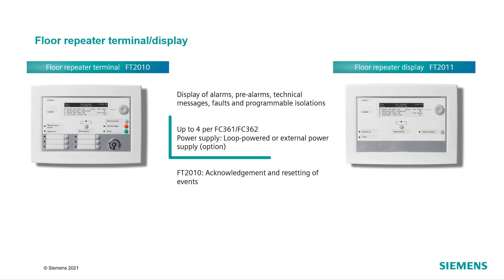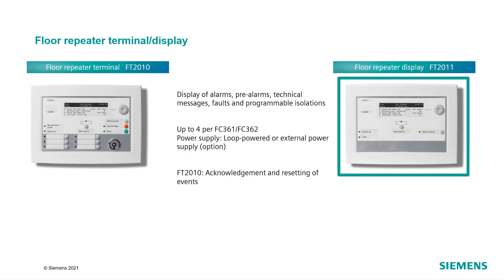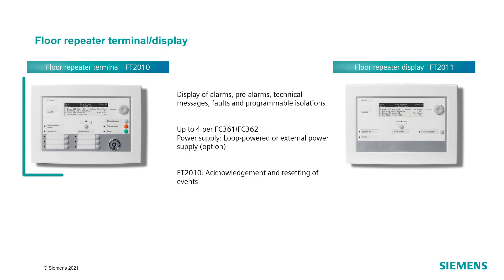They are part of the CNET and can be supplied via the loop or by using an external source. By default, the FT2010 and FT2011 show all events from the fire panel. The FT2011 is only a display, without any operation. In contrast, on the FT2010 events can be acknowledged and reset.